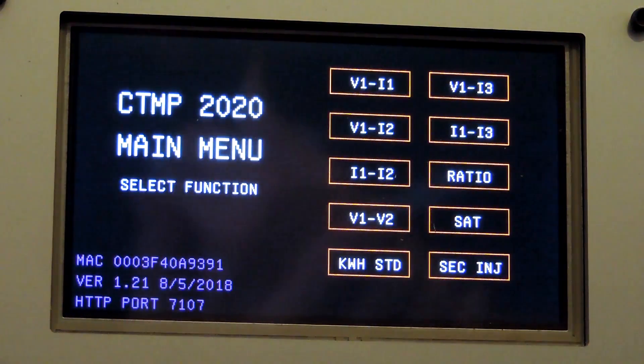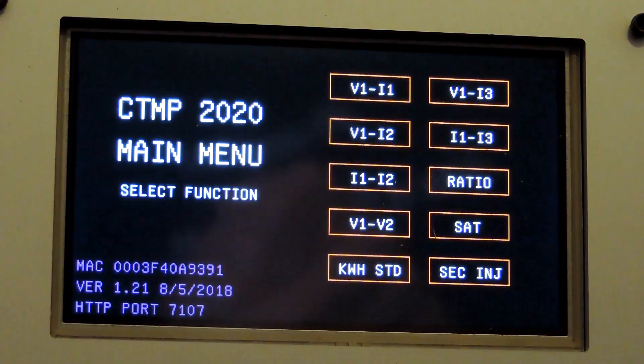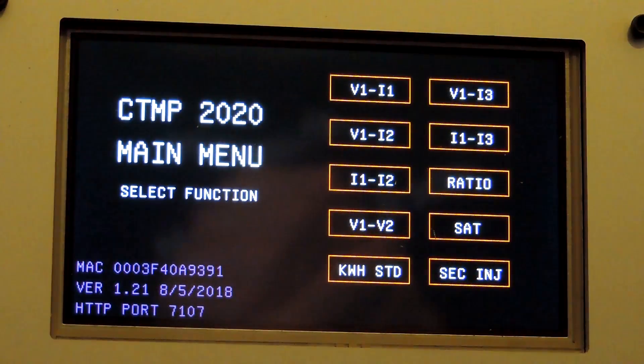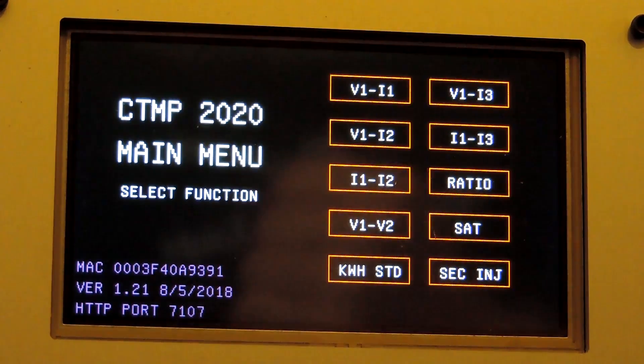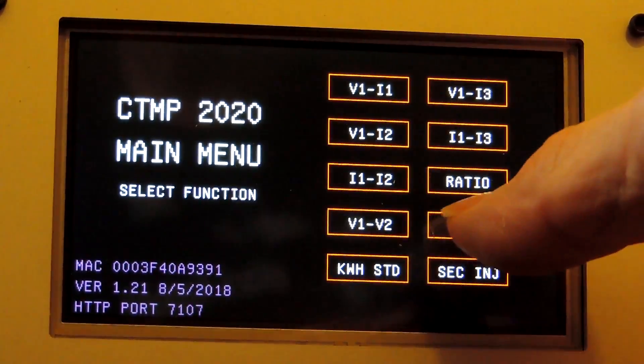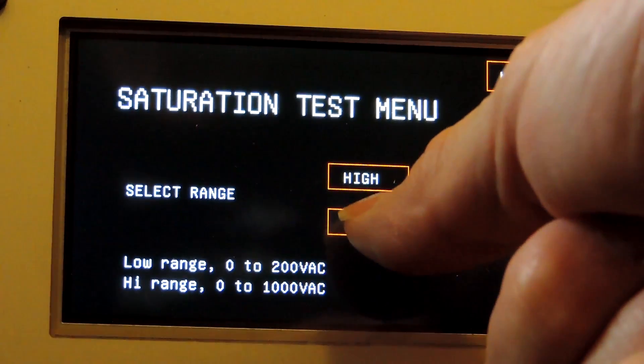Okay, we're starting from the main menu. This will be a multi-tap saturation test. If you would like to see the connection of the CT, that is in the ratio video and the ratio section of the instruction manual. So I'm going to press saturate low range.